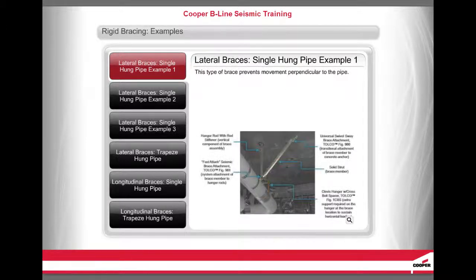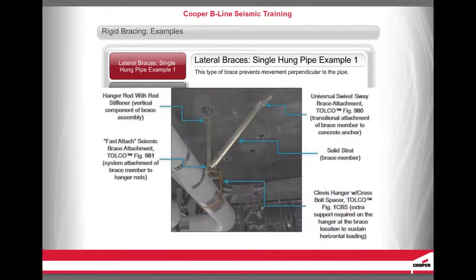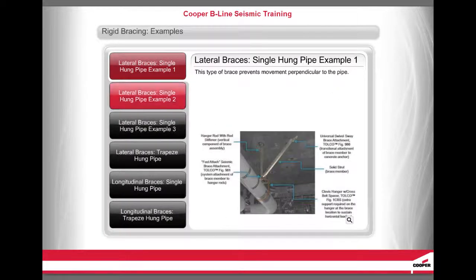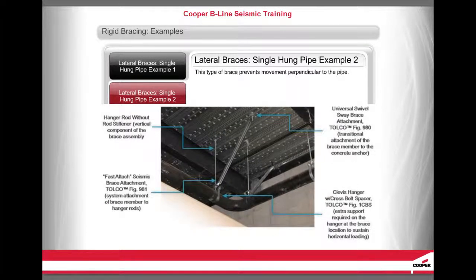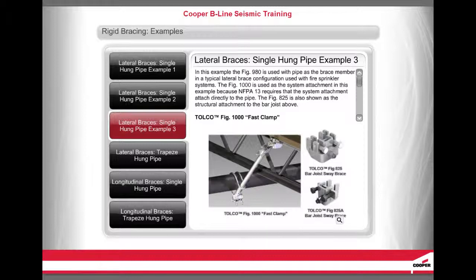This type of brace prevents movement perpendicular to the pipe. In this example, the Figure 980 is used with pipe as the brace member in a typical lateral brace configuration used with fire sprinkler systems. The Figure 1000 is used as the system attachment because NFPA 13 requires that the system attachment attach directly to the pipe. The Figure 825 is also shown as the structural attachment to the bar joist above.